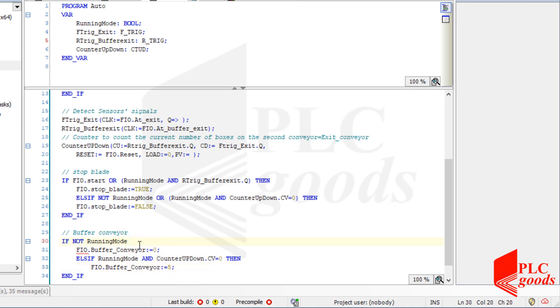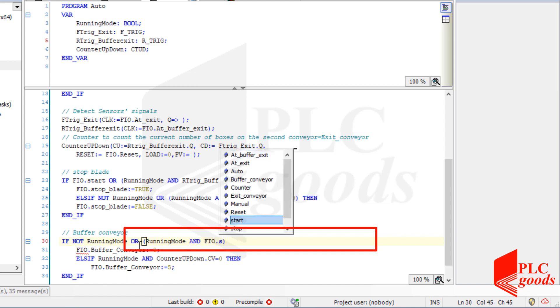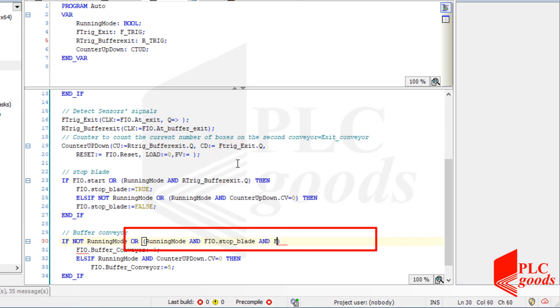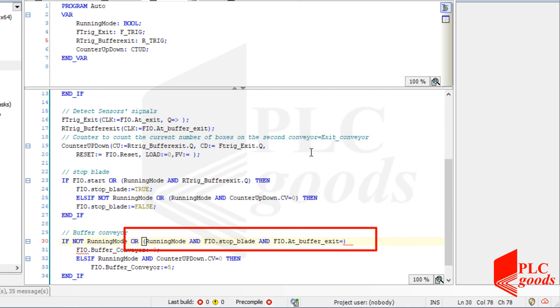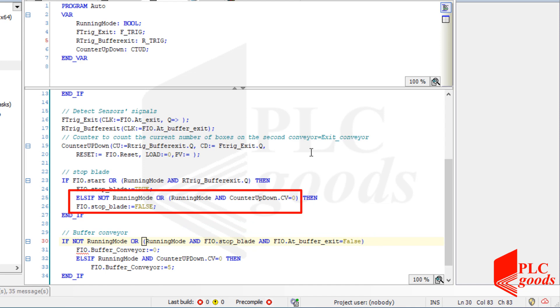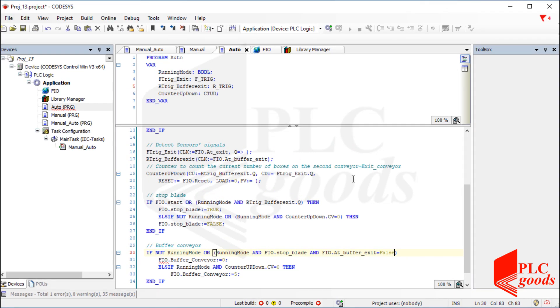Note that there is another condition: my controller must turn off the buffer conveyor when it's in running mode. Naturally, when the system is in running mode and the stop blade is enabled and also there is a box behind the stop blade, my controller must turn off the first conveyor until the current box on the second conveyor is transferred completely. After that the stop blade will be off and the counter value will be 0, and in consequence my controller will run the first conveyor again. I've finished the programming step — let me compile it.